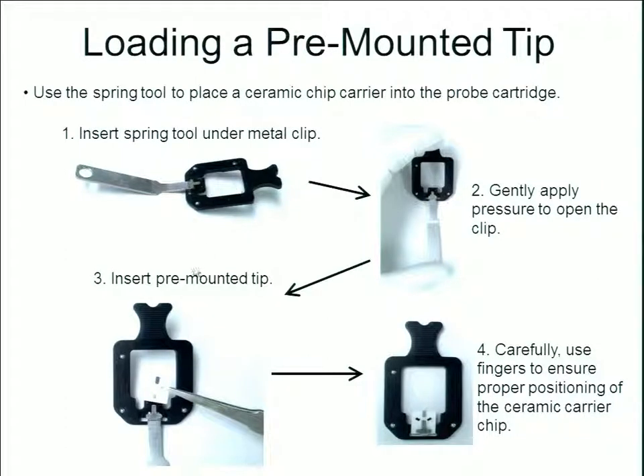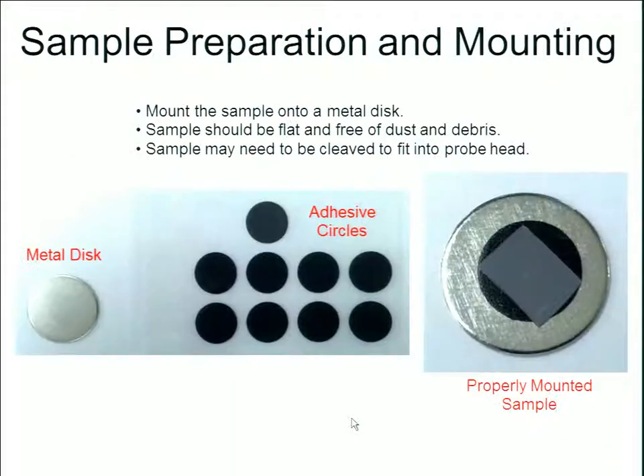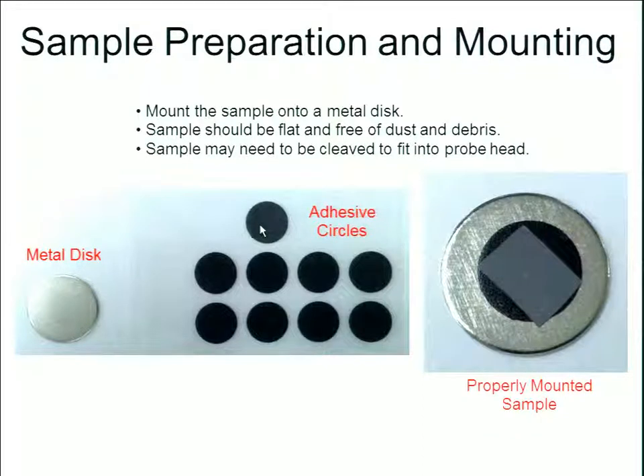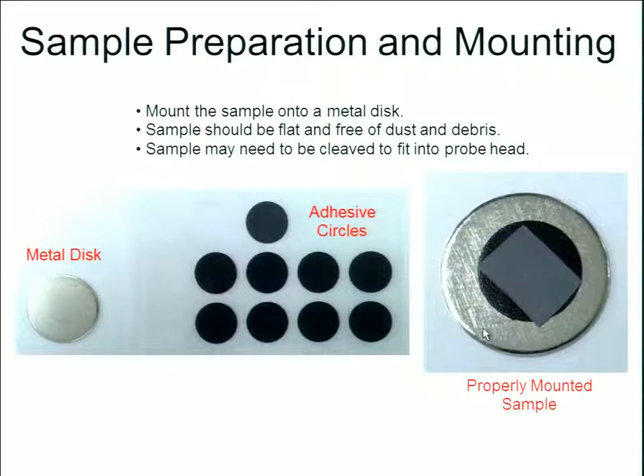To load the tip: use the spring tool to open the spring, insert your pre-mounted tip on the white chip carrier, and carefully clip it into place. Then take the whole probe cartridge and insert it into the probe head. For mounting a sample, use a small metal disc with double-sided carbon sticky tape, carefully press your sample onto the tape, and place the disc on top of the piezoelectric scanner.